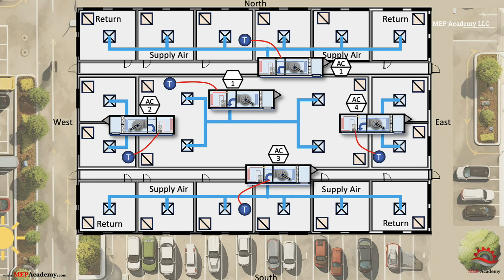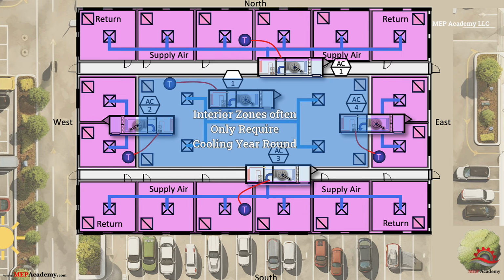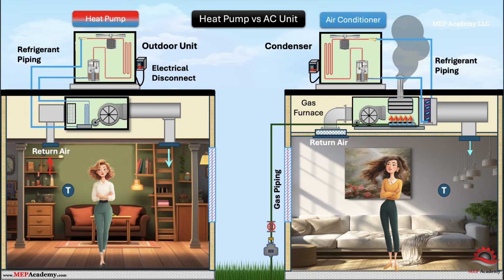When to use each system. Choose a heat pump if you're conditioning exterior zones. You're in a mild or warm climate. You want all-electric systems. You need both heating and cooling. You're designing for decarbonization and electrification. Choose an air conditioner if the zone is interior and cooling dominant. Heating is not required. You want lower upfront cost, or a separate heating system already exists. Choose an air conditioner plus a furnace if you are in a cold climate and you already have a gas infrastructure.